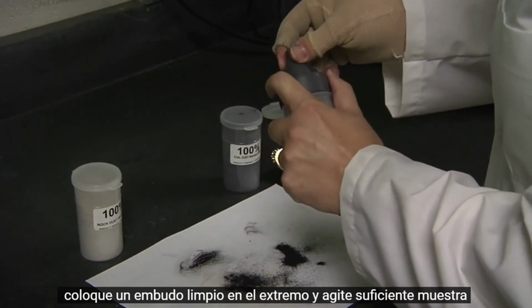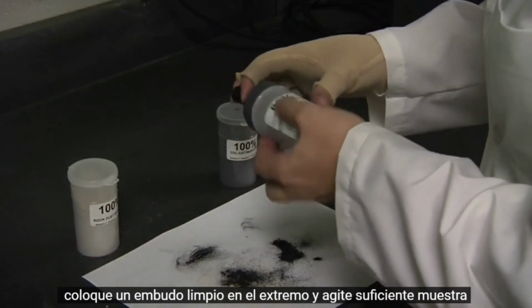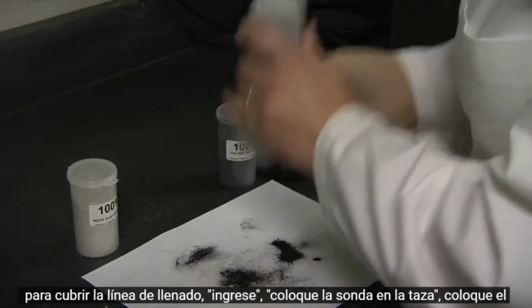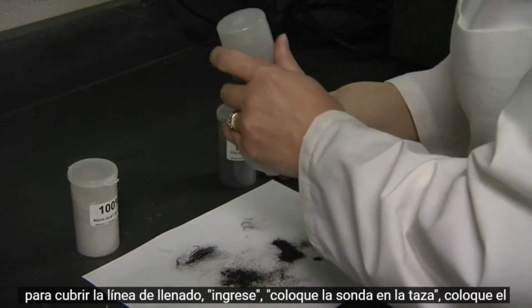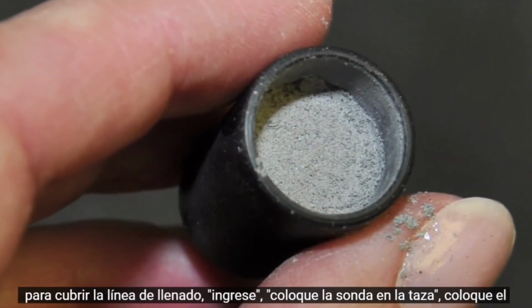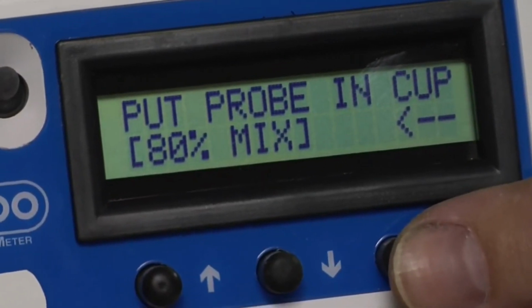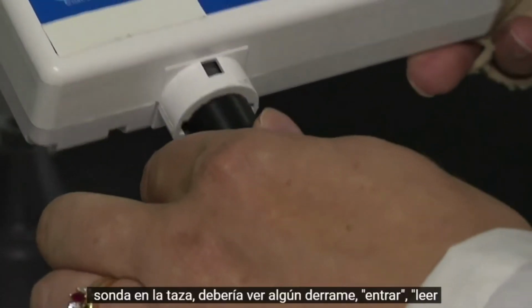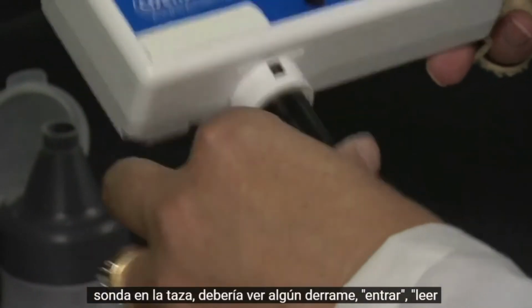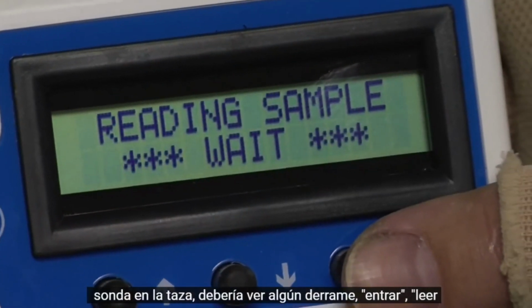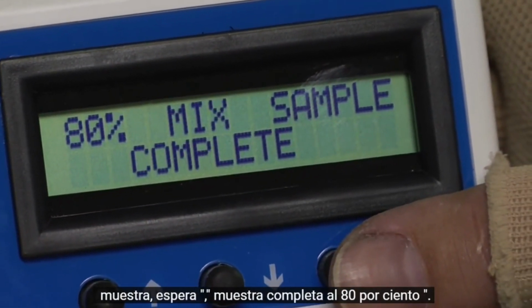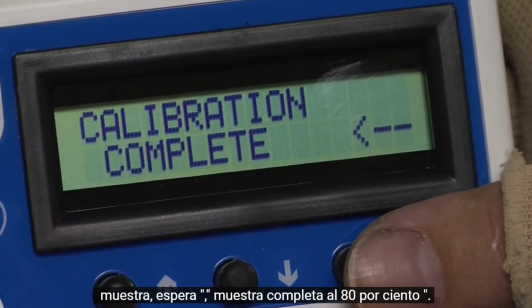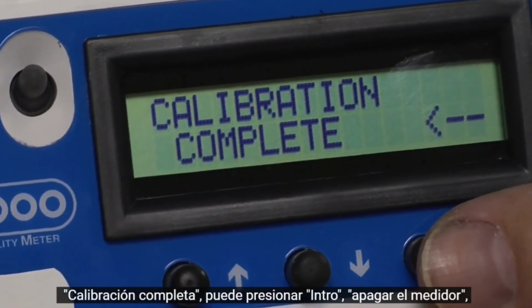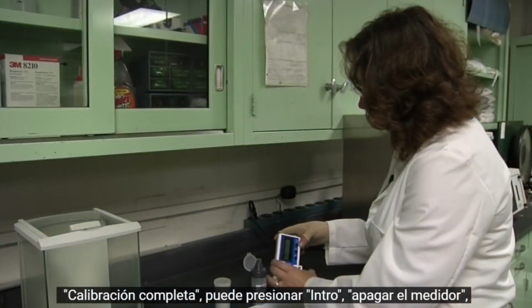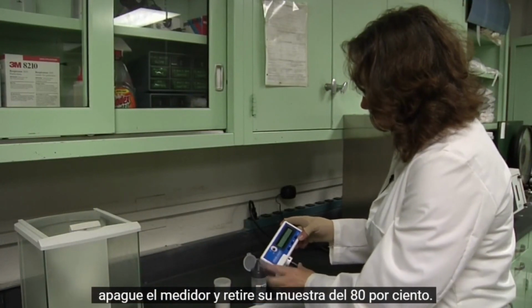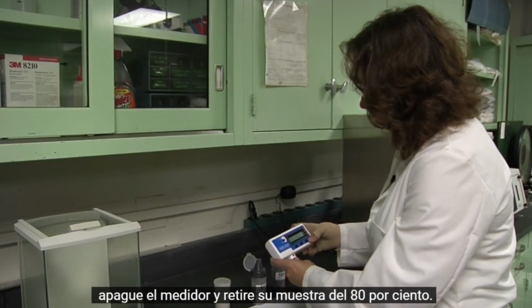Attach a clean funnel to the end and shake out enough sample to cover the fill line. Enter. Put probe in cup. Put the probe in the cup. You should see some spillage. Enter. Reading sample. Wait. 80% mix sample complete. Calibration complete. You can hit enter, turn off meter, turn the meter off, and remove your 80% sample.